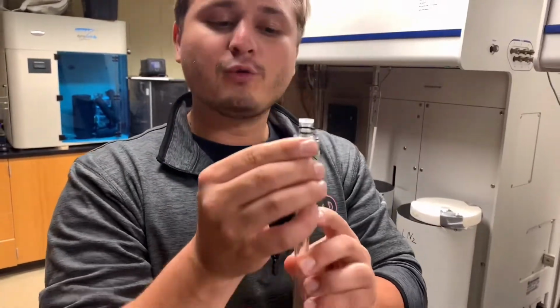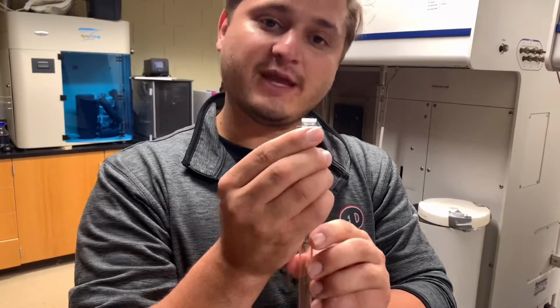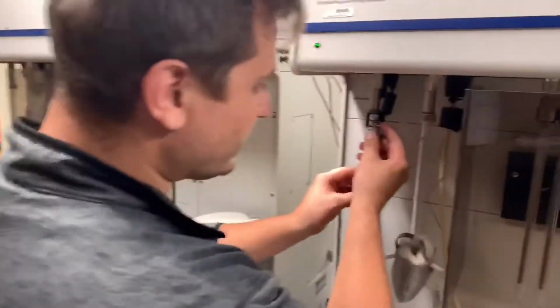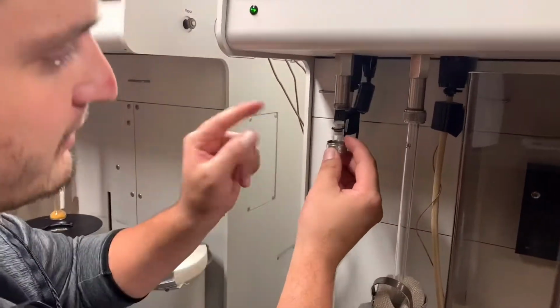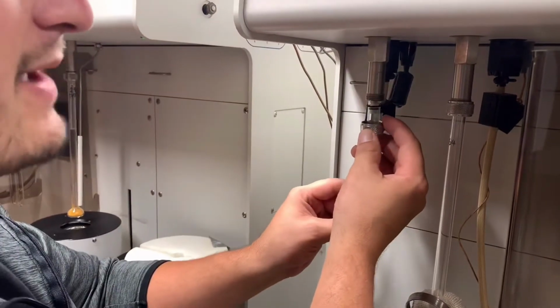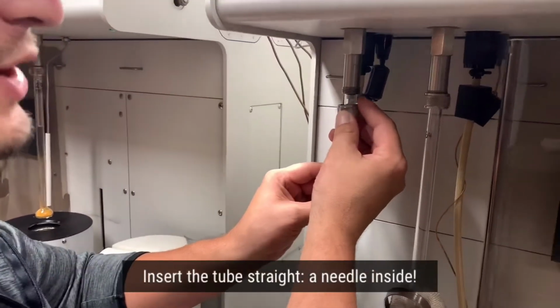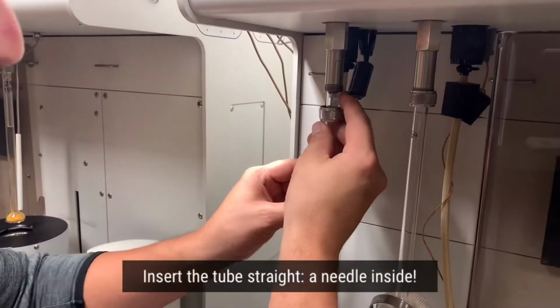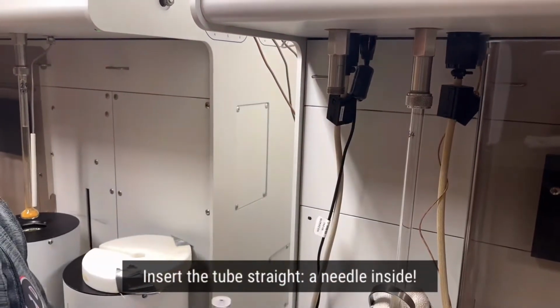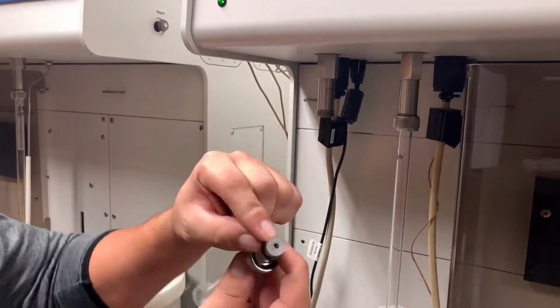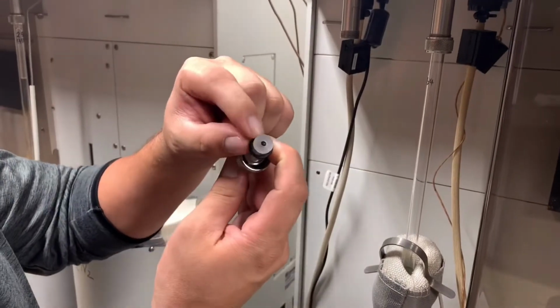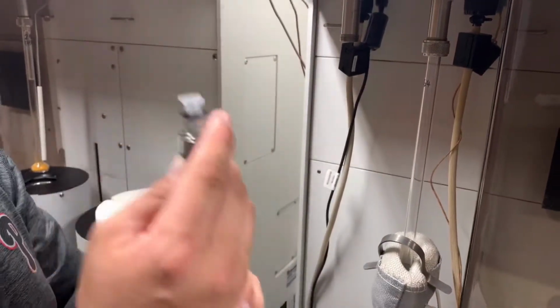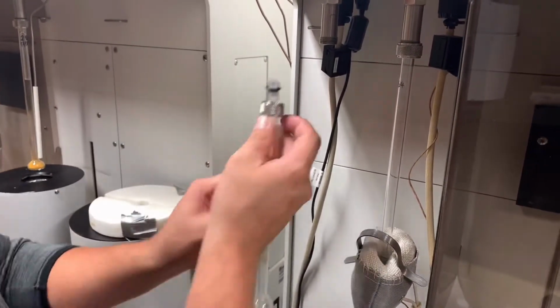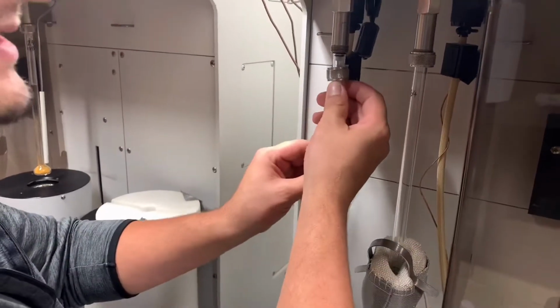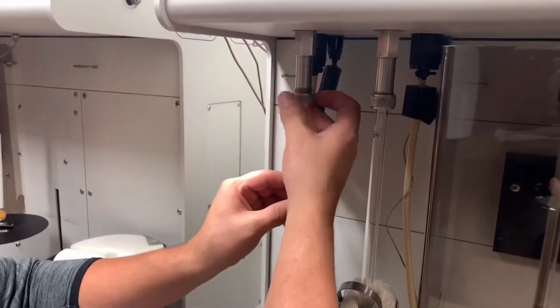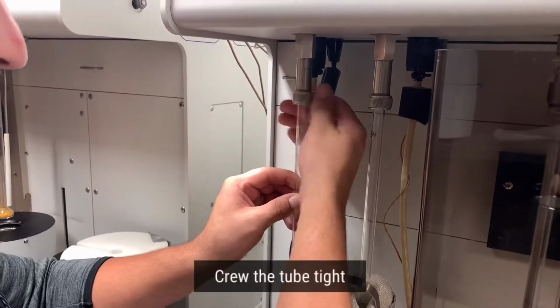After that, we will raise up the other 2 pieces of the connection and bring it over here to the port. When you're putting this on, you need to make sure that you insert the tube straight up and down, as there is a needle that is underneath here. And that needle is what pushes down on this sample tube cap in order to let air or gas in and out of the sample tube.